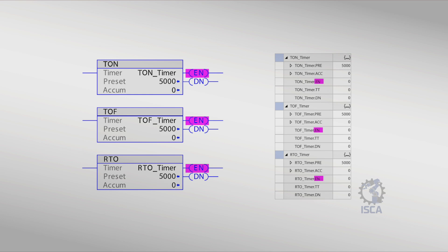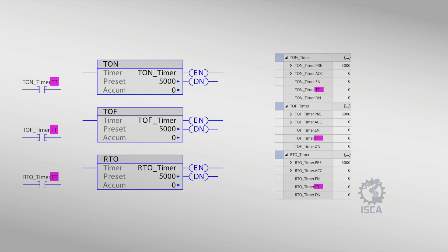Enable bit, EN, indicates the timer has been enabled. It will go high or turn on when the input controlling is true and stays true. Timing bit, TT, indicates that the timer is timing and will turn off once it reaches its preset value.